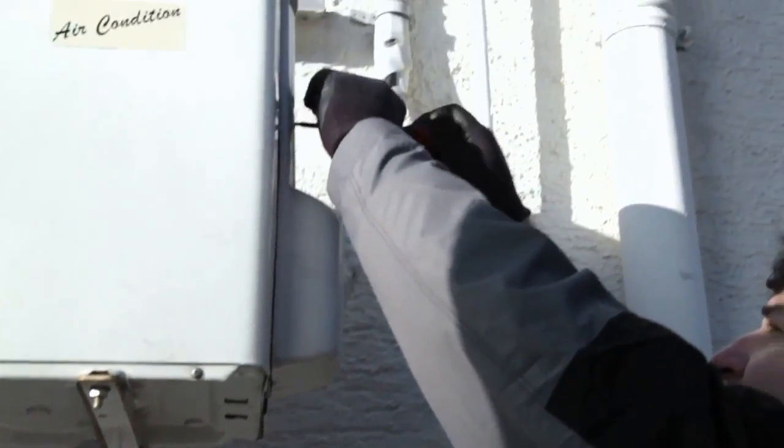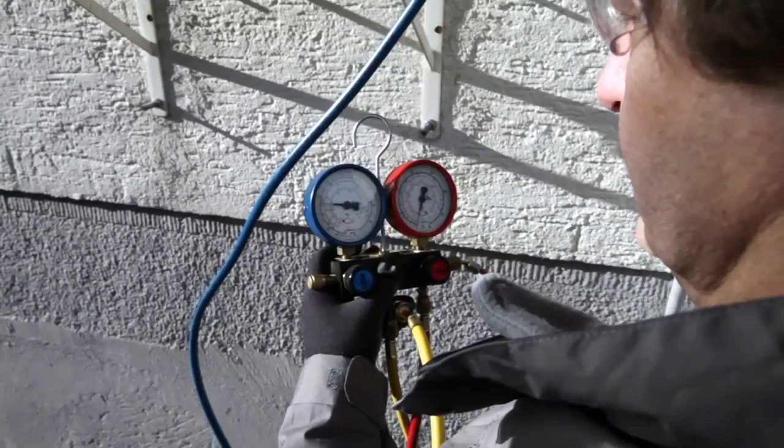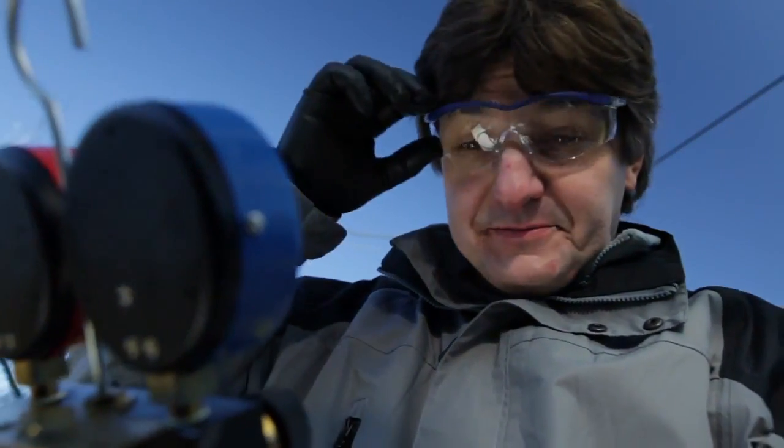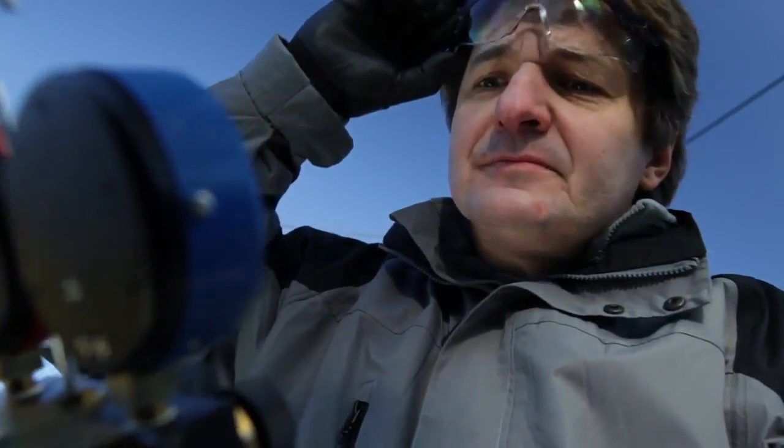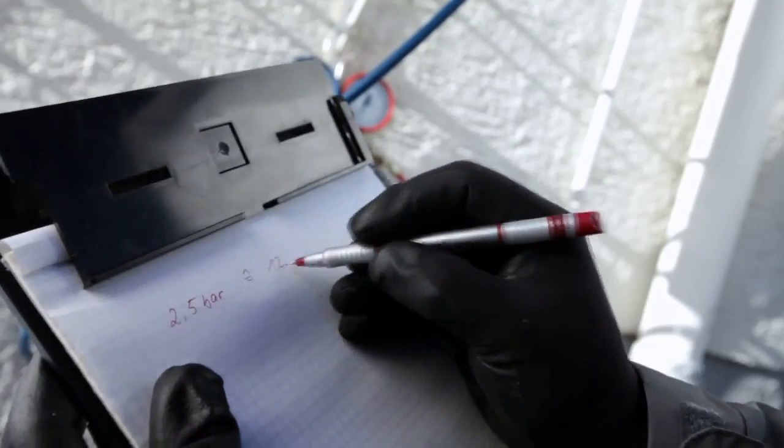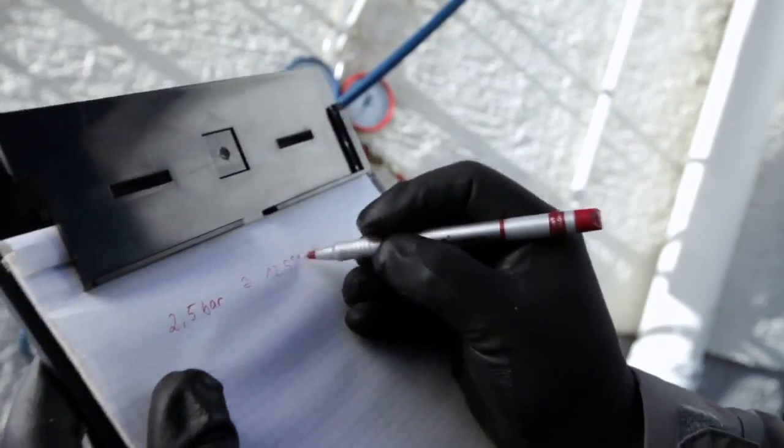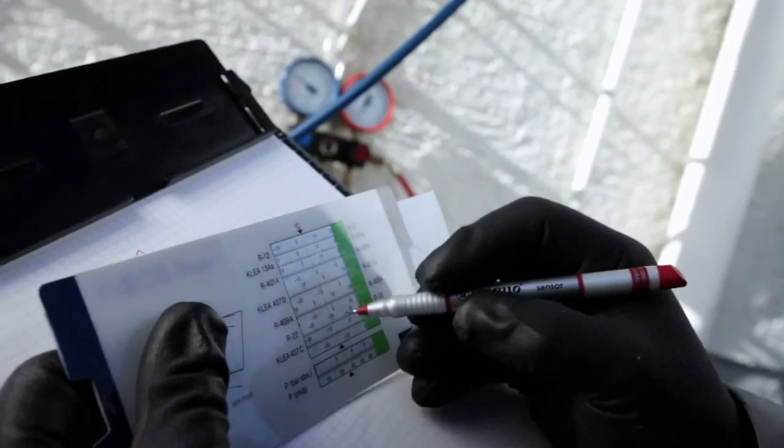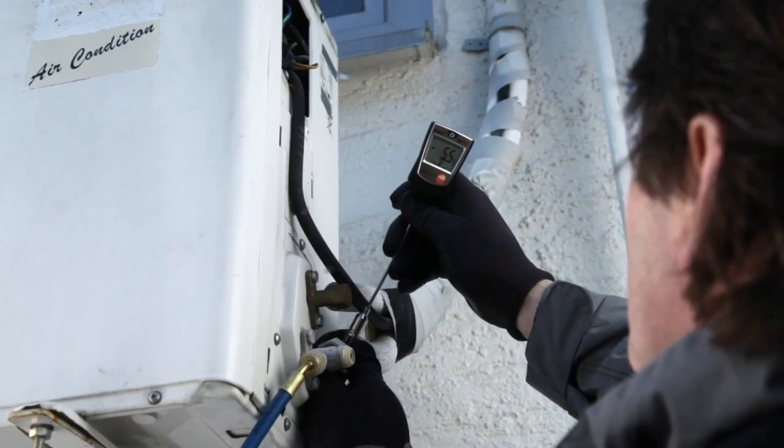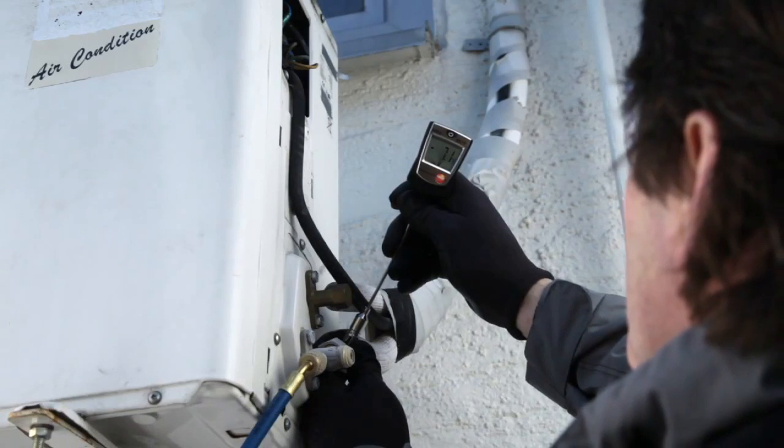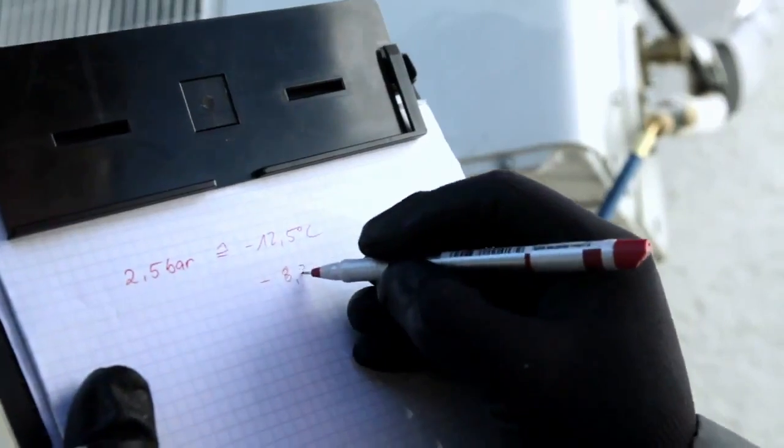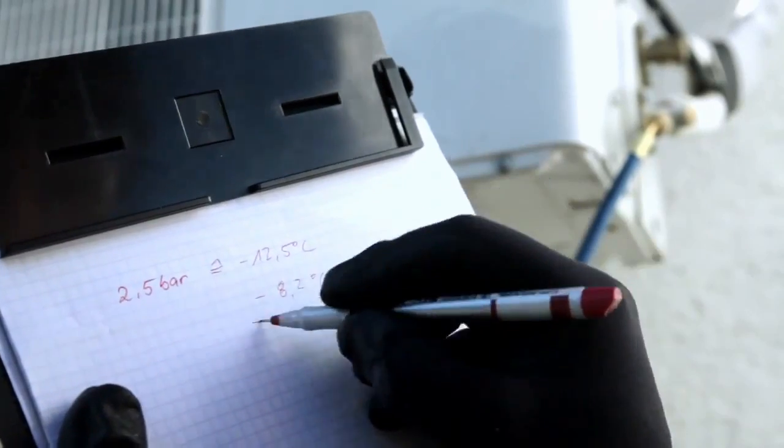Reading off the pressures is difficult since the manometer display often fluctuates. Interpretation of the saturation temperatures, exact read off of the tables, inaccurate time consuming temperature measurement and finally calculation errors can also occur.